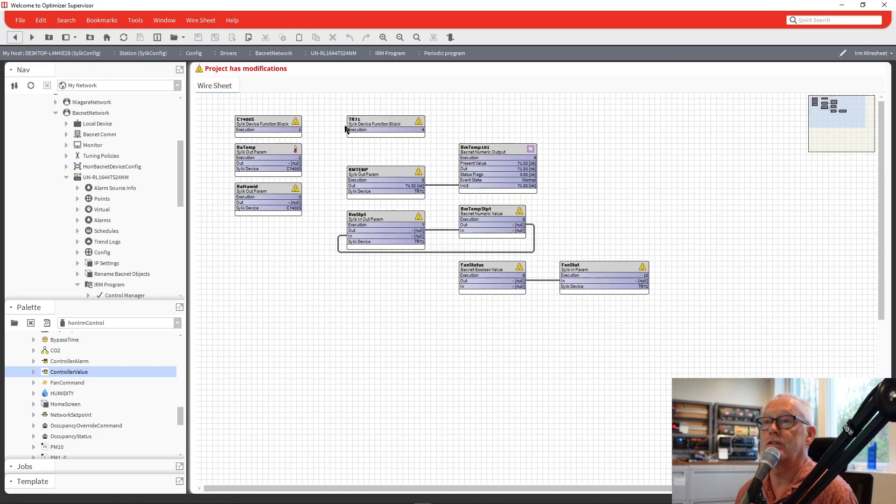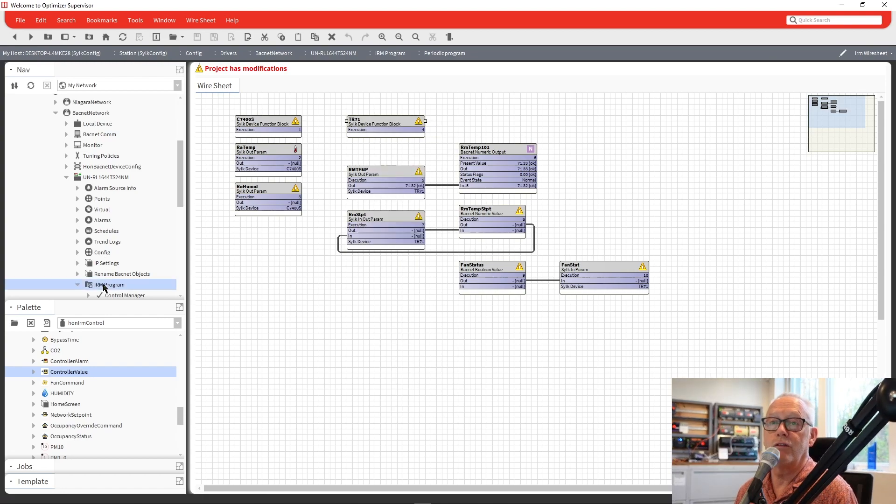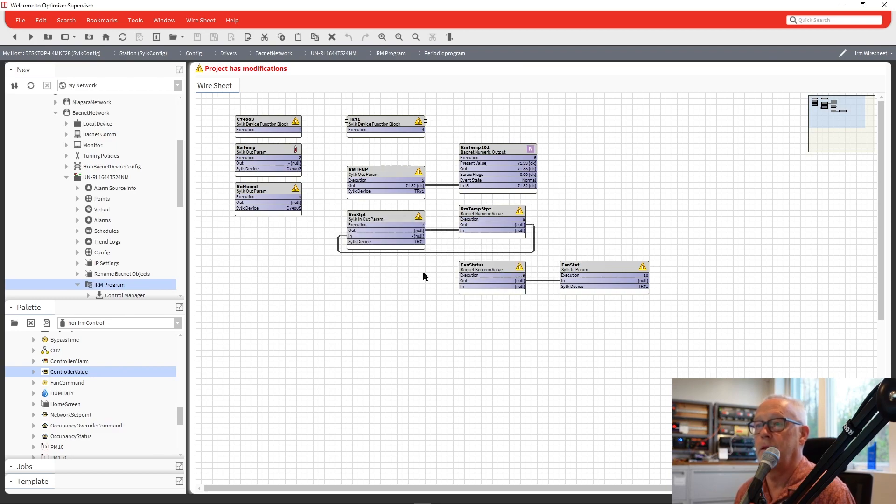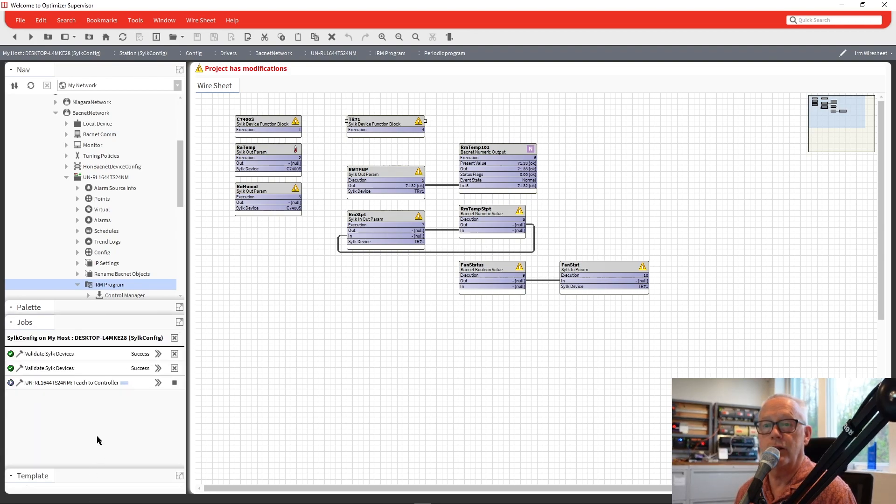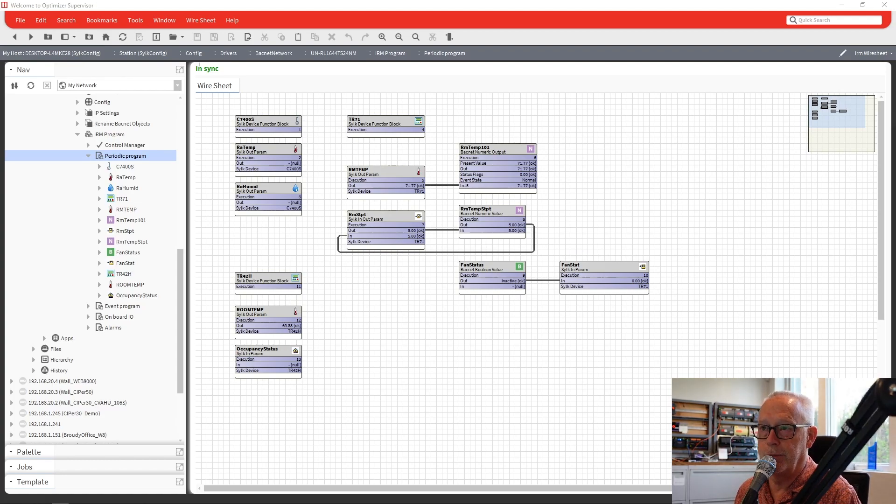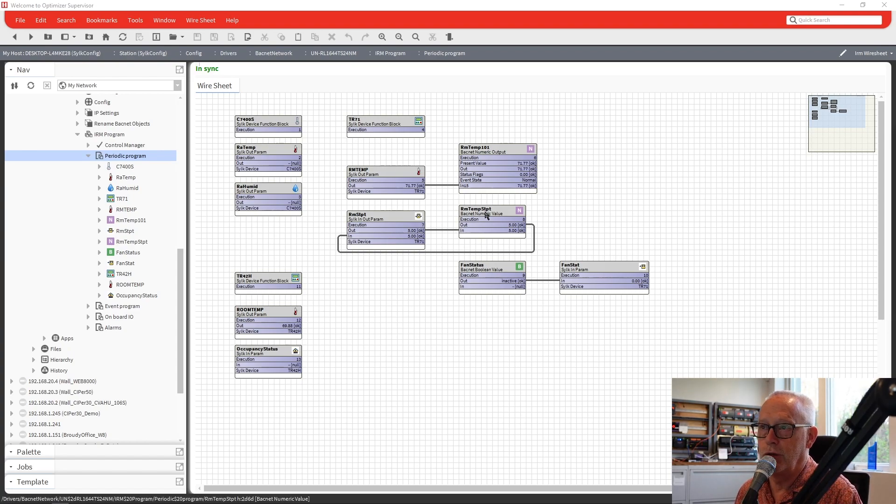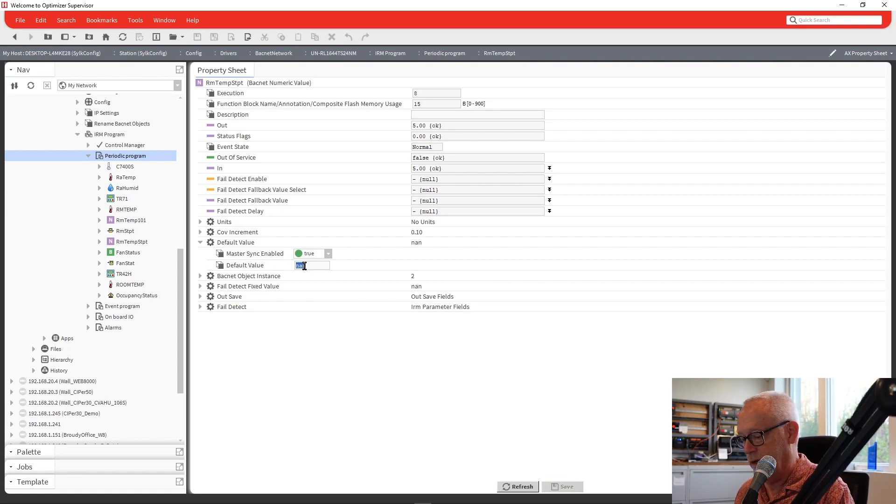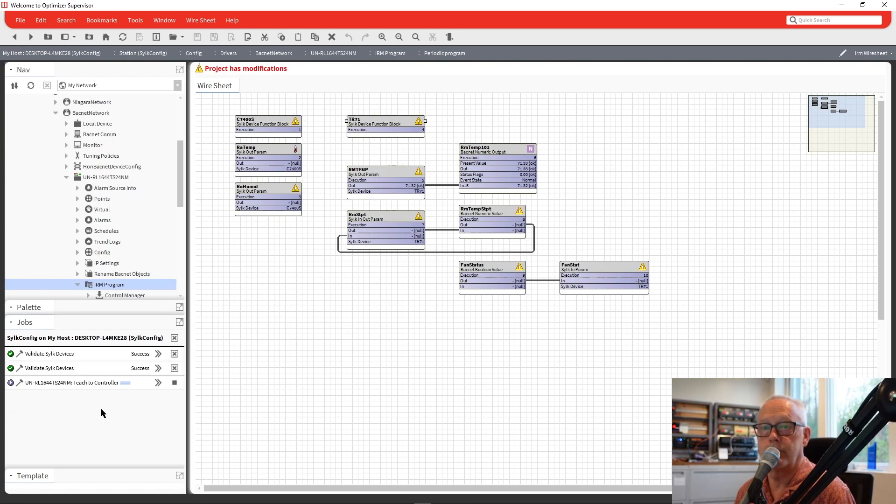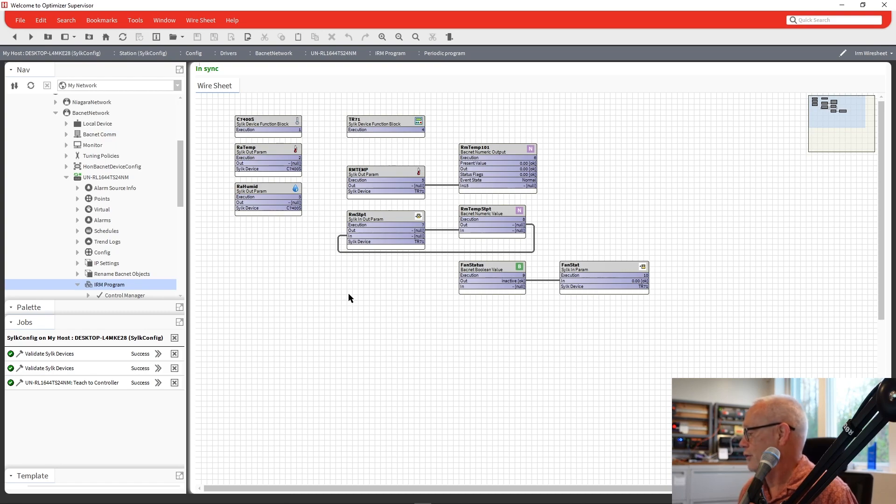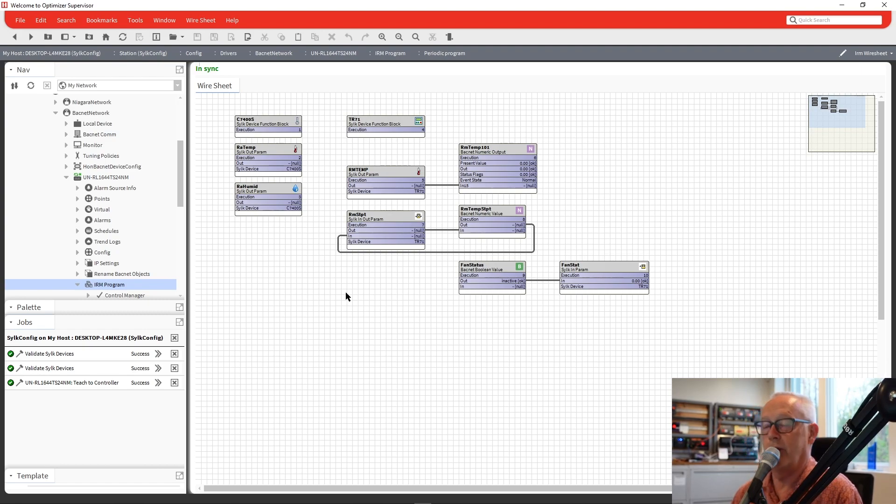Validation was good. So we should be able to go in there and turn around and re-download or re-teach to the controller. We'll try it with just this regular teach instead of a full teach and we'll see if it allows us to get that downloaded. One thing you have to make sure you do is to create a default set point so that when your TR-71 comes back on and you go to change the set point, there isn't a zero there or a null value. So to do that, we're going to go into the BACnet point for the room set point, go to the default value, and make sure you put in a value that you wanted to come up with the first time through. And while that's doing, okay, it's finished and you'll see all the icons updated so we know we have good values. If I look over on my wall module, I have the, it's blank right now because it's still downloading the necessary changes to the Xeo. And once that finishes, it'll show up on the display there and we can go in there and work with that.